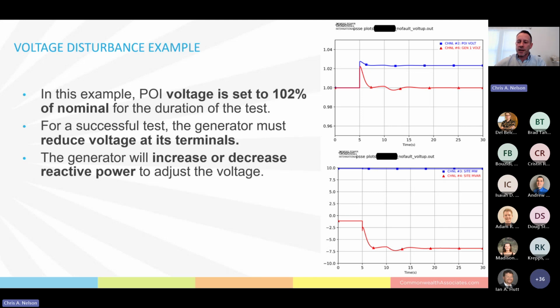And the way it actually does this, it doesn't have a voltage control so much as it injects VARs or subtracts VARs from the system, and that affects the voltage. So this is an over voltage case, so the generator runs with negative VARs to lower the voltage, basically how it affects that.